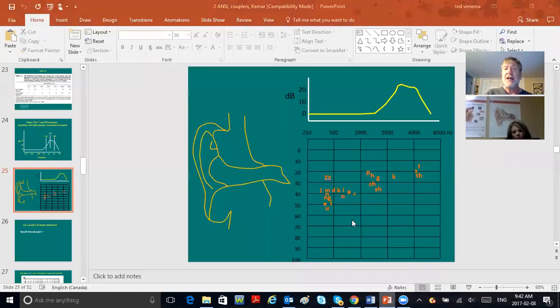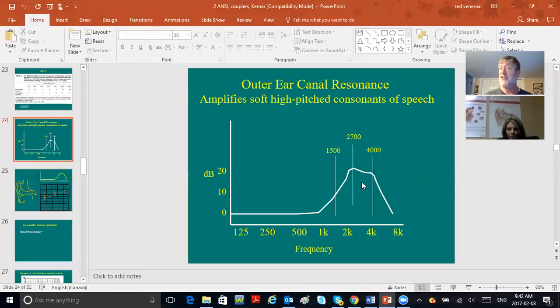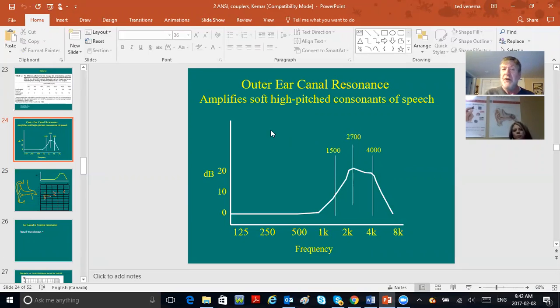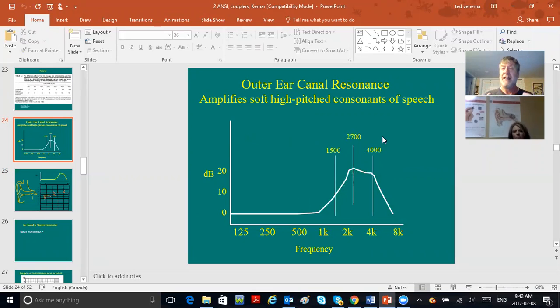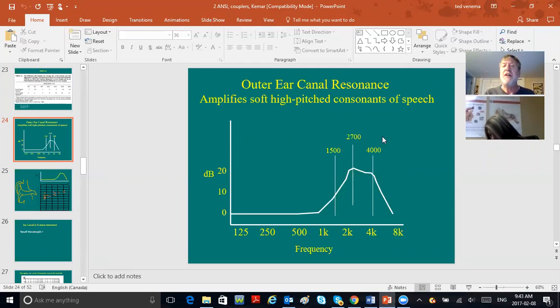Instead of comparing aided to unaided hearing thresholds, you stuck a tube in the ear and measured the real ear unaided response, then put the hearing aid on top of the tube. With the same sound coming in, you got a real ear aided response. Real ear aided minus unaided gave you the insertion gain. You checked whether that matched the target of the fitting method—same idea as functional gain, but a totally different and much faster way of measuring it.